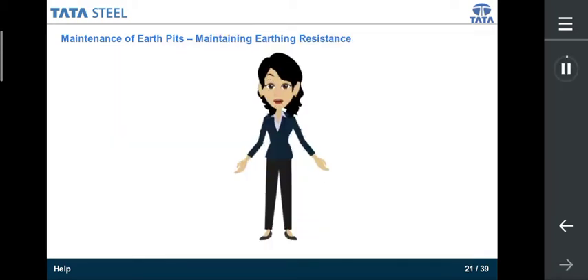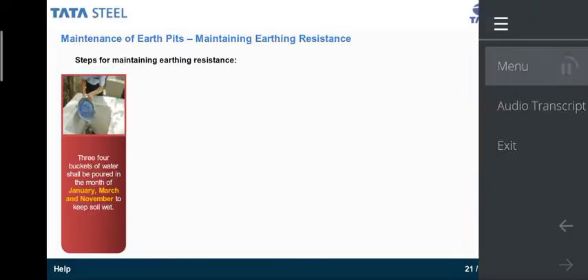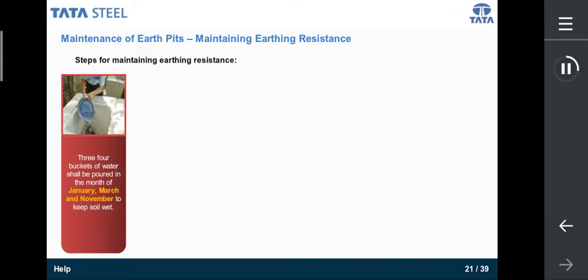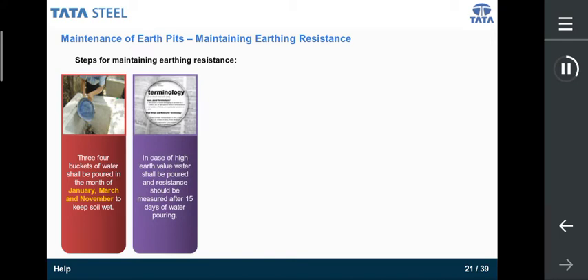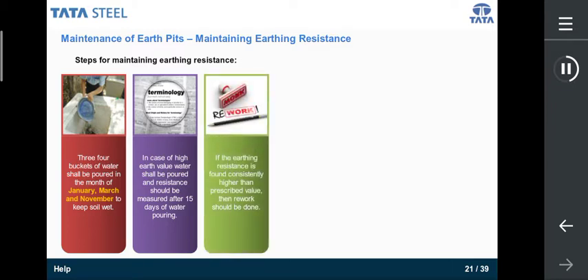We had learned earlier that testing should be carried out in the dry seasons only, right? Now let us understand what needs to be done to maintain earthing resistance. Firstly, 3-4 buckets of water shall be poured in the months of January, March, and November to keep the soil wet. In case of high earth value, water shall be poured and resistance should be measured after 15 days of water pouring. If the earthing resistance is found consistently higher than the prescribed value, then rework should be done.